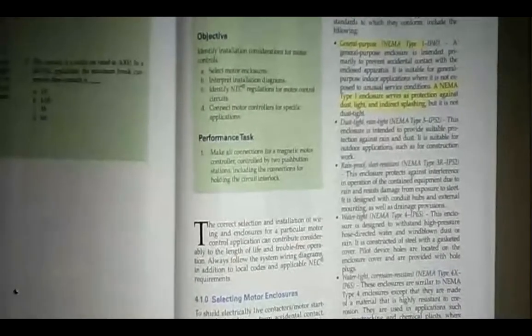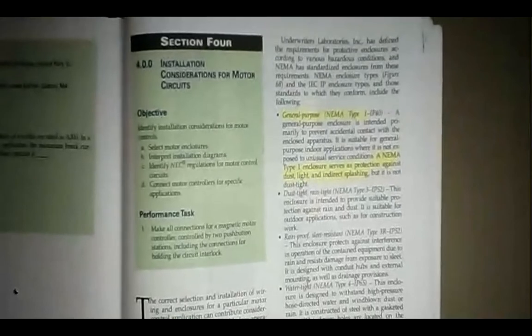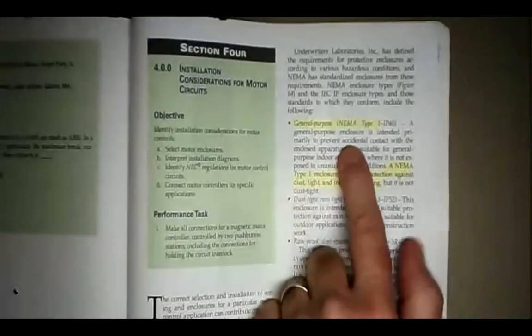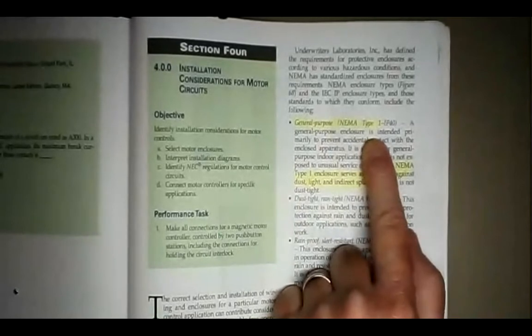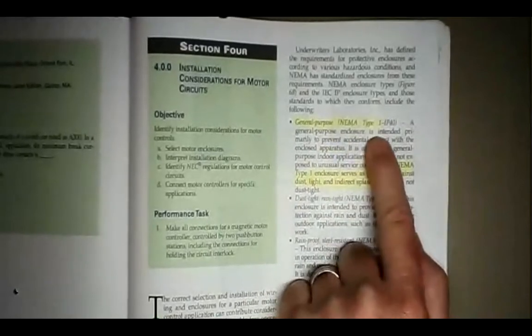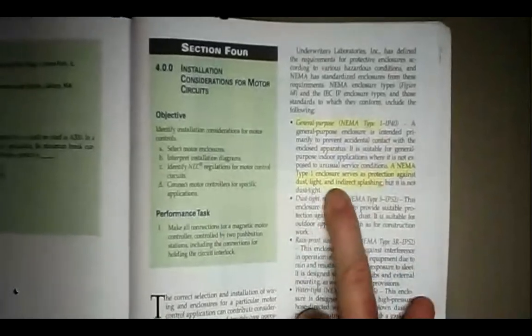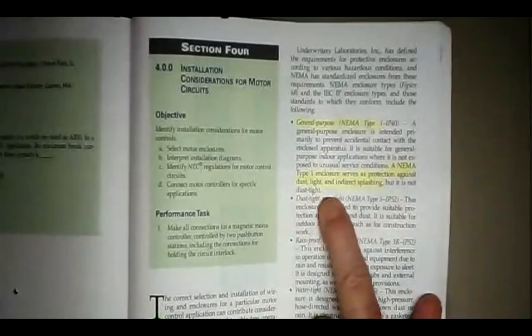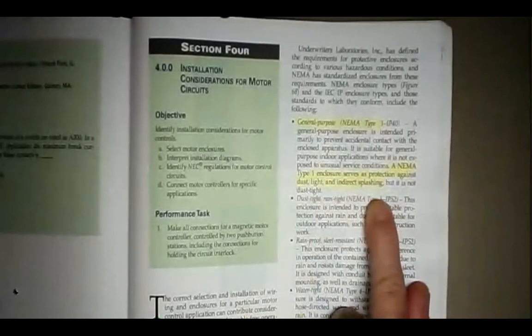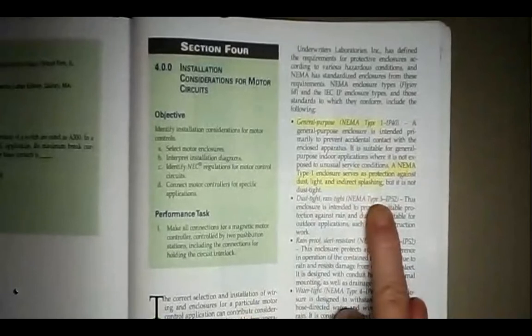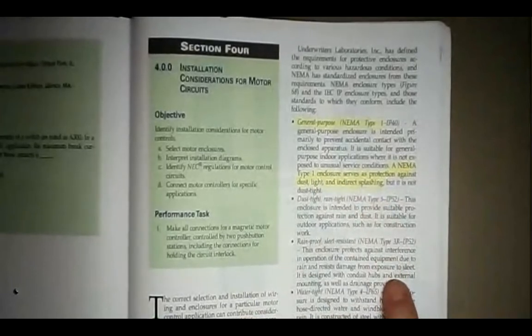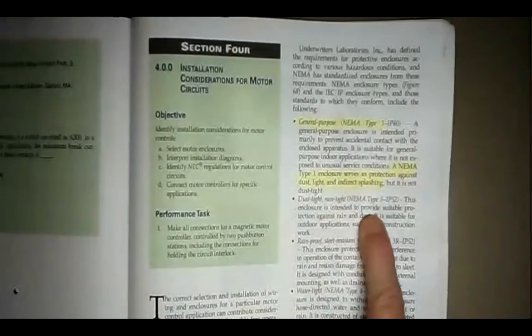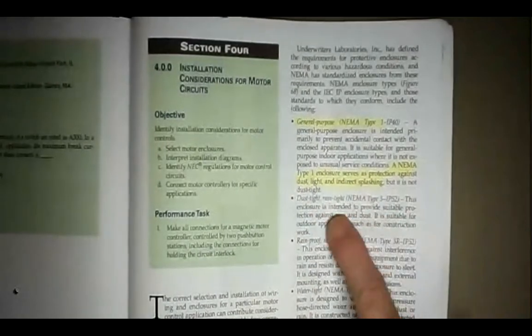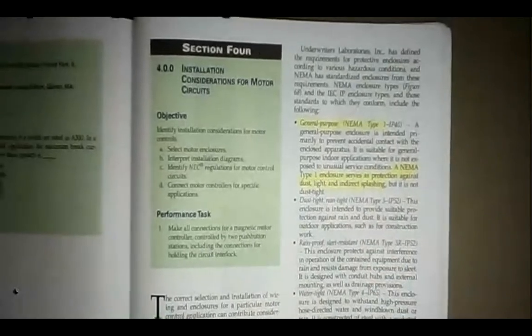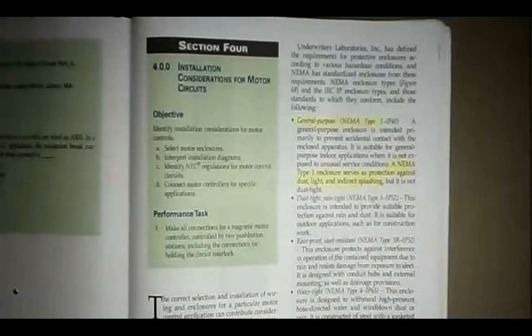installation considerations. Over on the right-hand side of page 57, general purpose, NEMA, National Electrical Manufacturers Association. Type 1, a general purpose box, type 1 box is for indoor use. A NEMA type 1 enclosure serves as protection against dust, light, and indirect splashing. They're not meant for outdoor use. You need a NEMA 3 if you're going to put it outdoors. Here's dust tight, rain tight, NEMA type 3. So type 3 is for outdoors. And if it's for heavy rain, it has to be a type 3R, just so you know. Okay.